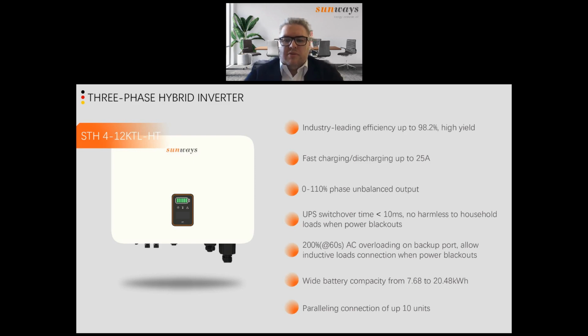And the very important thing is that when it switches over to off-grid mode within less than 10 milliseconds, it can last 200% AC overloading for 60 seconds, allowing more powerful devices to start up, because as you know, many devices at the beginning of work have peak consumption, so many inverters tripped because of overloading.